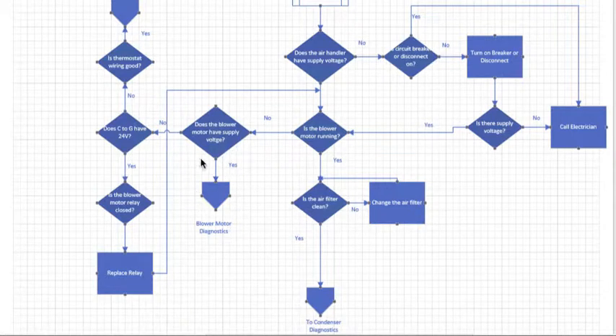So we have left one thing here: blower motor diagnostics. If your blower motor has supply voltage and the motor's not running, we need to look at the blower motor diagnostics. Let's face it, the air handler is just a thing to move air. All we're doing with the air handler mechanically is moving air across a coil and out through the ductwork. So we have very few parts that can go bad. It comes down to a blower motor, a transformer, some relays, and supply voltage. Check all of those parts.